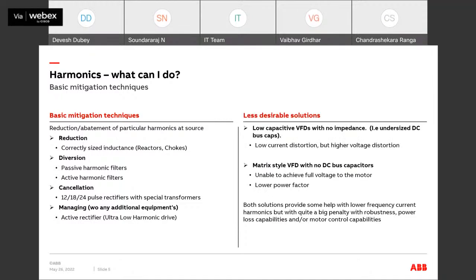There are other techniques also which are less desirable solutions. You can have low capacitance VFDs with no impedance, but they result in low current distortion with a higher voltage distortion. Matrix style variable frequency drives are also there, where we don't have DC bus capacitors, which are unable to achieve the full voltage to the motor and have a lower power factor. Both solutions can work, but they carry big penalties in terms of robustness, power loss capabilities, and motor control capabilities.